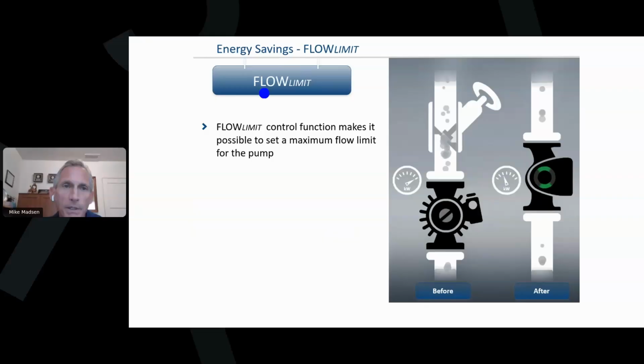With these smart pumps, now you can tell the pump electronically, hey, I want you to limit your flow. And so what we would do is we would set the coil rating as the flow limit. So if your coil is rated for 50 gallons a minute, you set a flow limit in the pump of 50 gallons a minute, and you never overpump that coil. So by not overpumping that coil, that really helps you get better delta T back to your central plant.